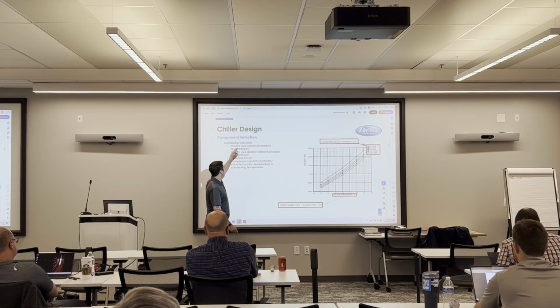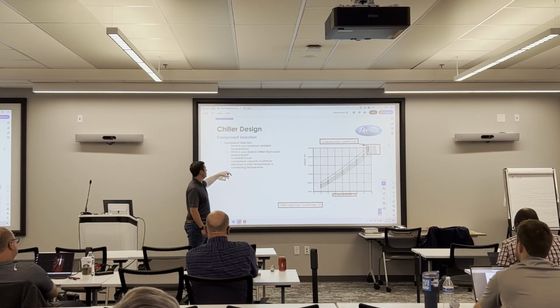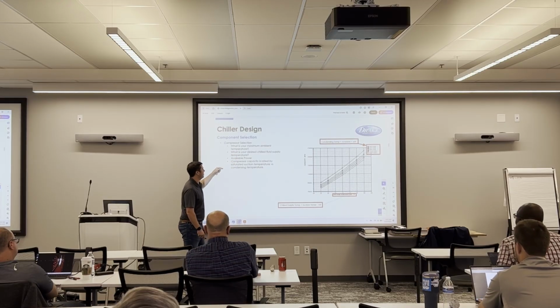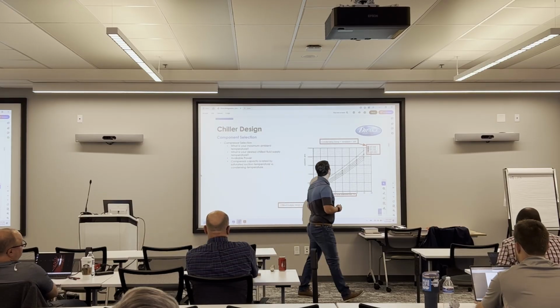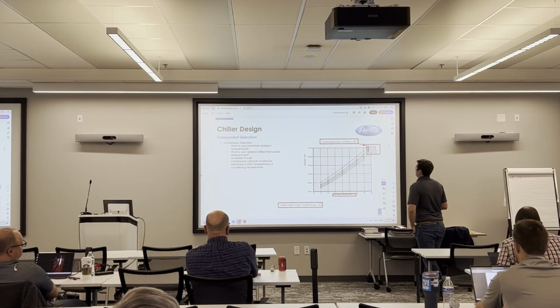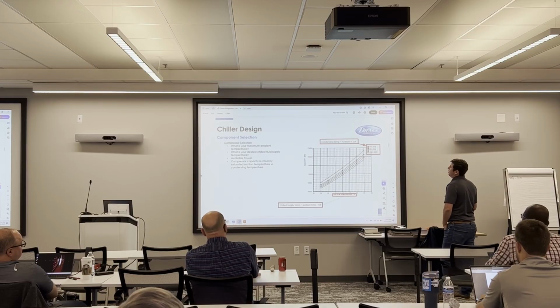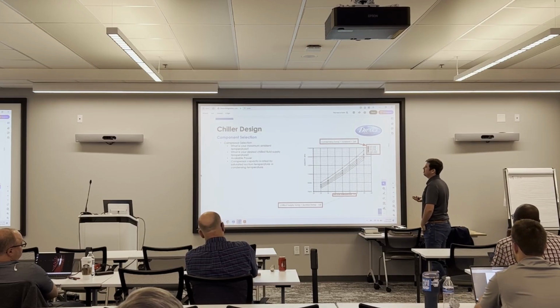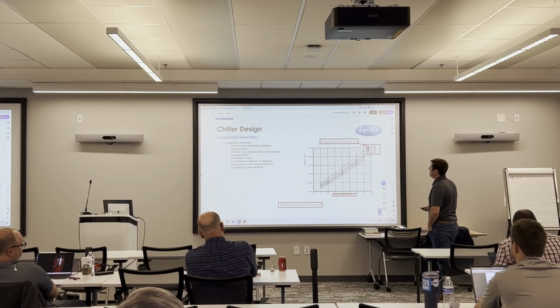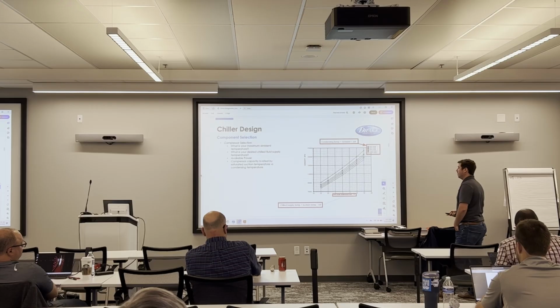If you get your maximum ambient and your chilled fluid supply temperature, that's enough information to figure out your condensing temperature and your saturated suction temperature. Up above here in red, our condensing temperature is going to be maximum ambient temperature plus 20 degrees. This number can fluctuate anywhere from 10 to 30 degrees, depending on how we want to go about sizing the coil. And then down below, your saturated suction temperature is going to be based on your chilled fluid supply temp.